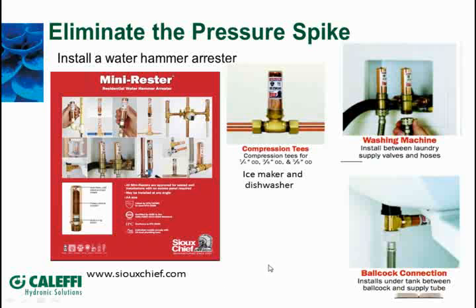I'll venture to say that a lot of times you've got some kind of condition causing the high pressure surge, and then the low and high pressure that's causing that little cartridge to jump off its seal there. So that's one fix. I've had guys on heatinghelp.com say that if you put another check valve in front of the backflow preventer, that check will take up that surge, and it won't affect the double check or the spool inside the backflow preventer.